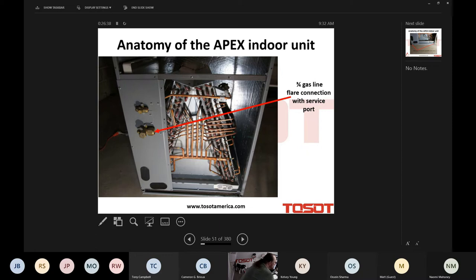One more point I want to make before I move off of that slide. Remember that the coil being charged, right? Think about all you're evacuating and leak testing. All you are evacuating and leak testing is the line set, right, baby? I mean, think about it. Both coils, both ends of those line sets are closed. You have a charged coil on either end. So the only thing you are leak testing and evacuating and possibly charging if you had to add more refrigerant is the line set itself. That really speeds up what can normally be a relatively slow operation, especially in evacuation. And again, I'll talk more about that as we move forward.